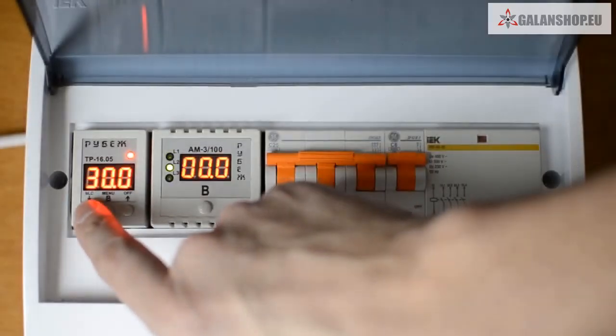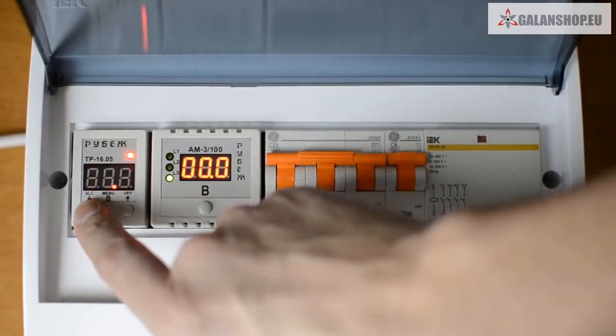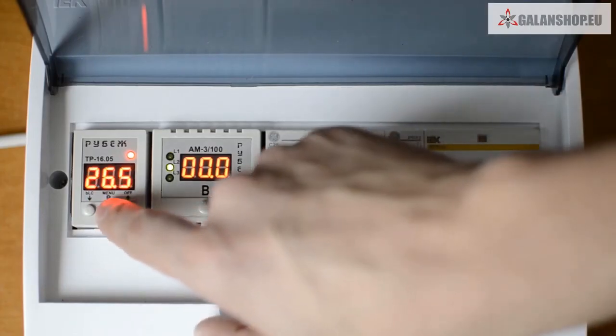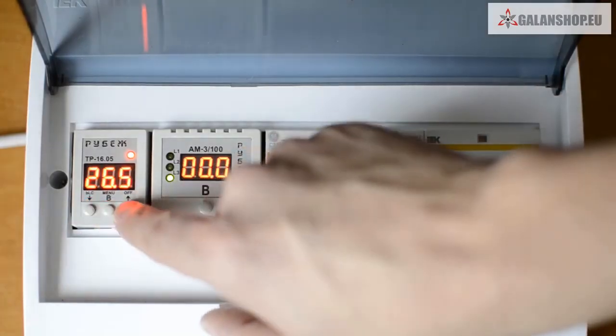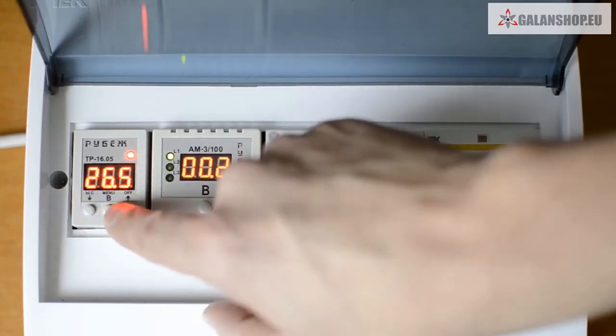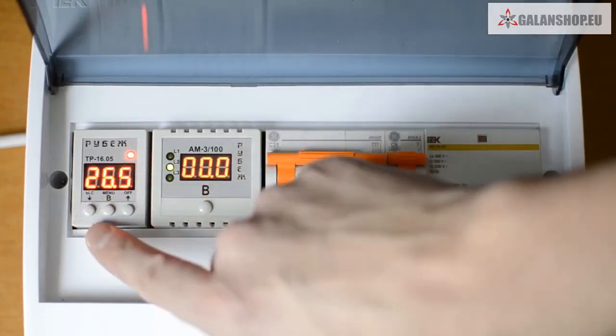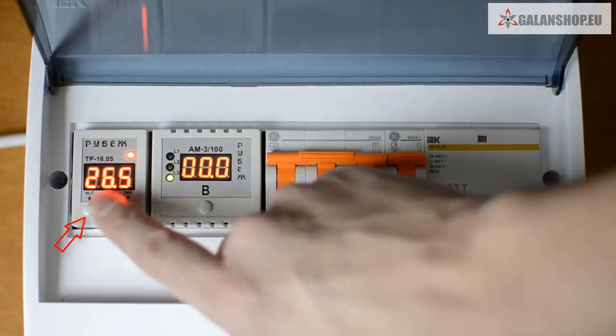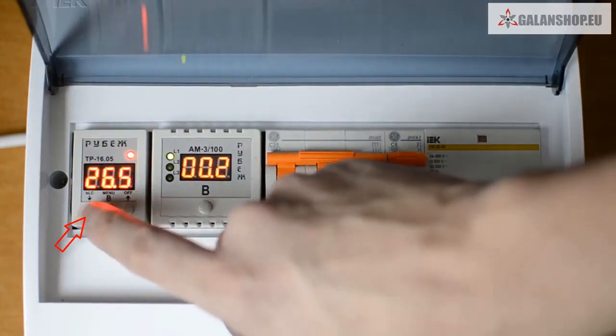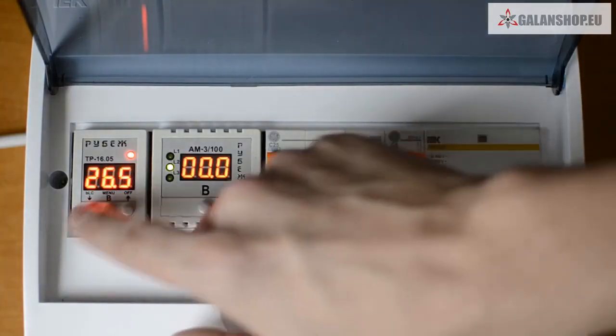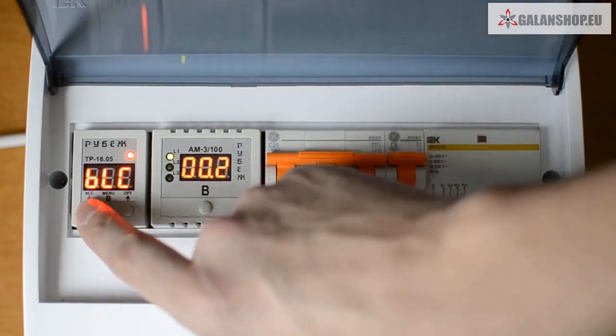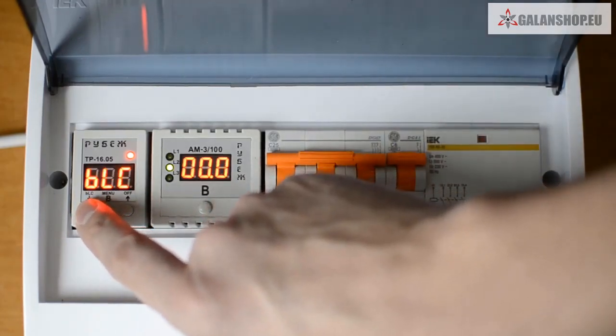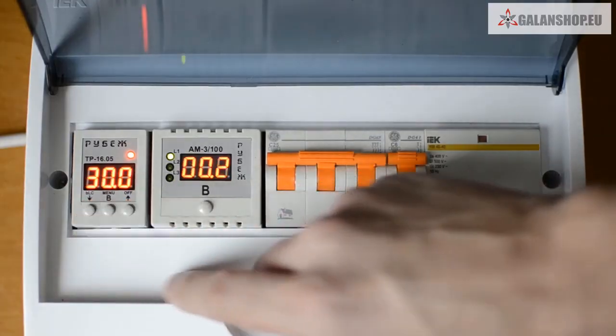How to set the electronic keypad lock. In order to lock the buttons, you need to press the down arrow button for 4 seconds. Now we have our keypad locked. After you do it and try to press any button, you will see BLC displayed on the screen. To switch it off, you need to press the down arrow button and hold it for approximately 5 seconds till the screen displays temperature. This function is used to avoid undesirable or accidental setting changes.